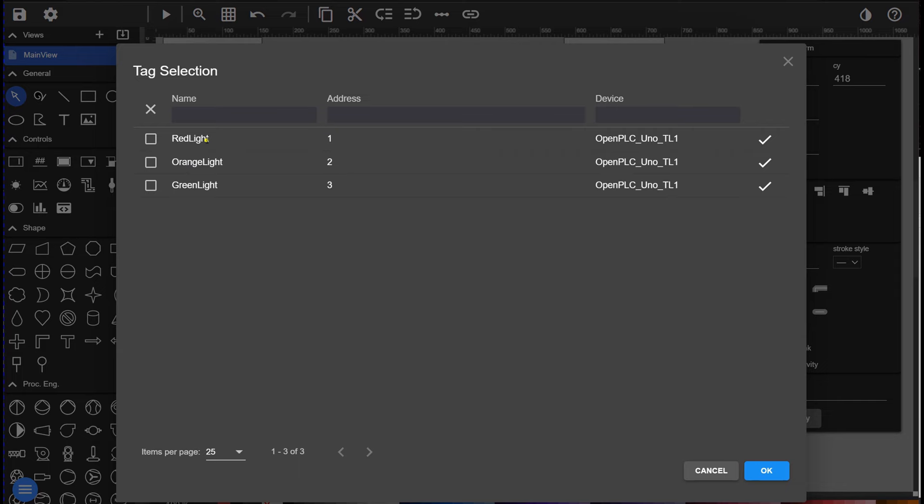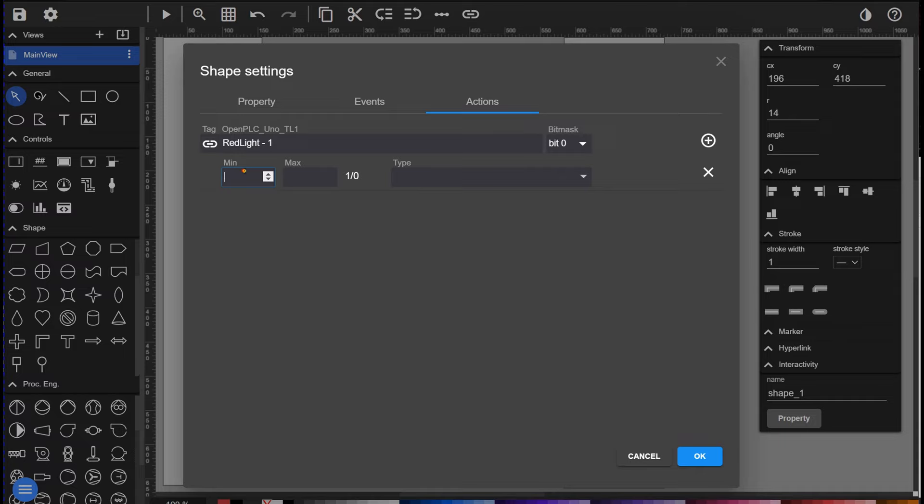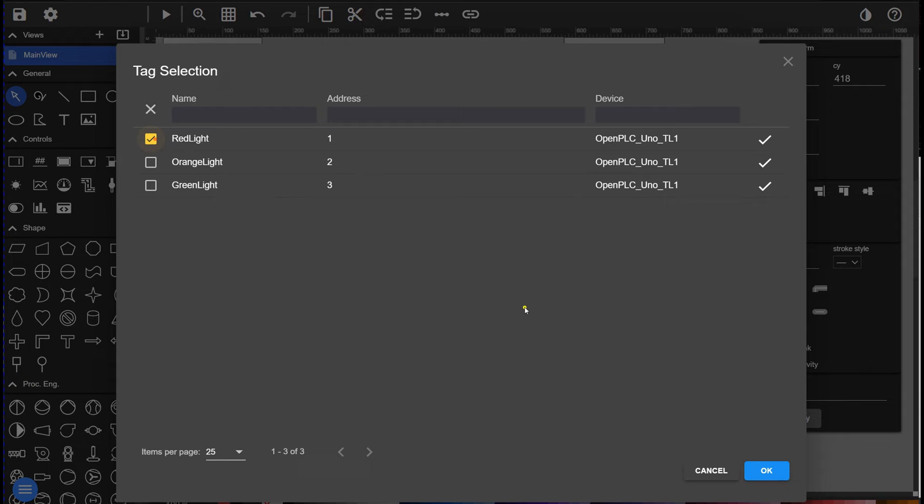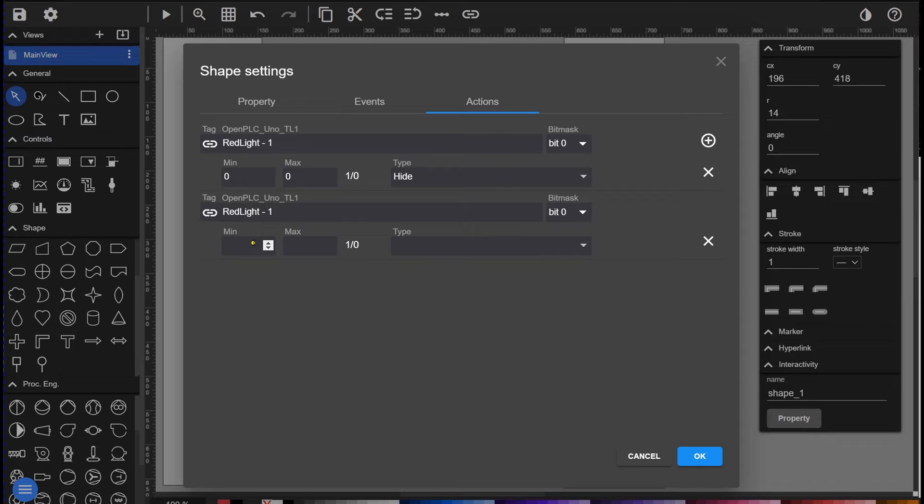First, we choose the red light tag and we also have to select the bit mask. In this case it is just a boolean, so we choose one. If the tag is zero, we hide the red circle. Then we need to add another action where we show the tag when the red light is on. We repeat this step for all the other lights.